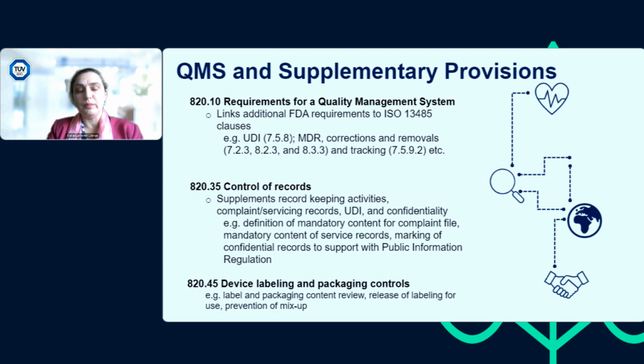Then the next example would be 820.45, device labeling and packaging controls. This is also very structured. If you look at 820.45, it talks about label and packaging content review, release of labeling for use, prevention of mix-up of material, and they define at what steps throughout the product realization process those reviews are required, what types of QC checks are expected to be implemented, and they take an additional step above what's currently documented in 13485.